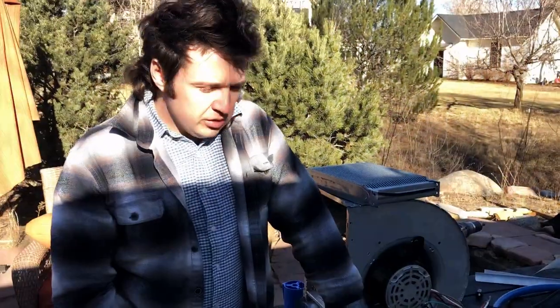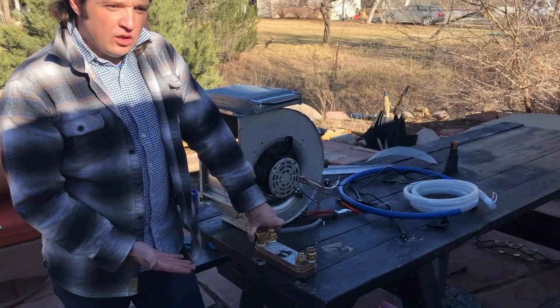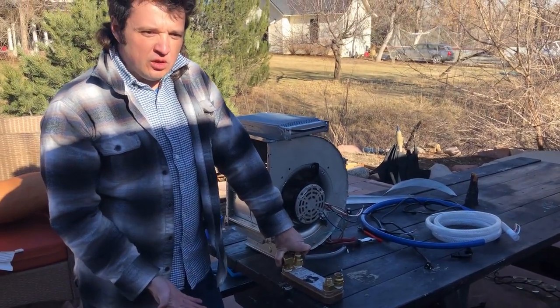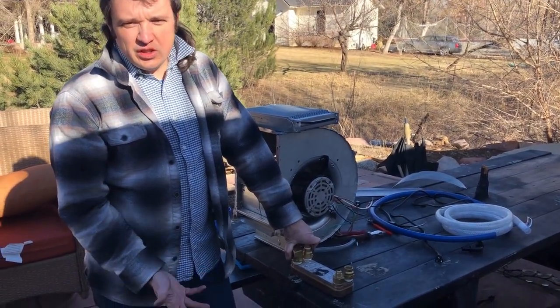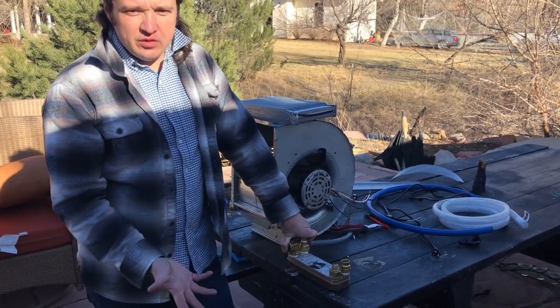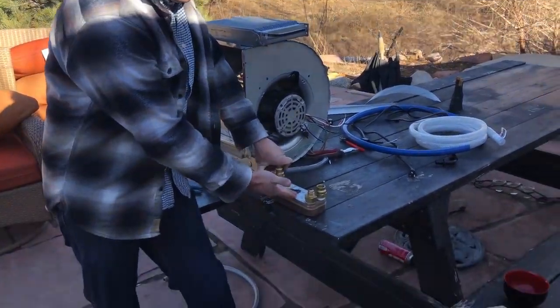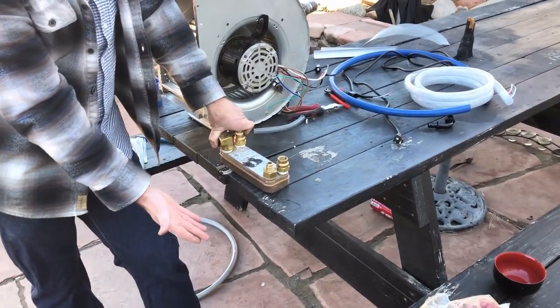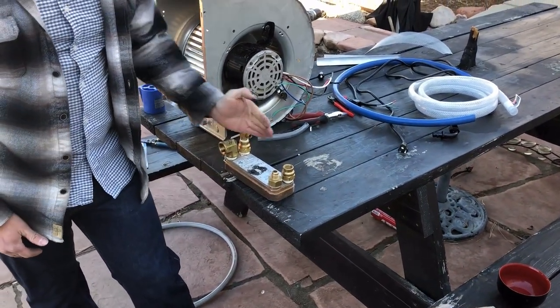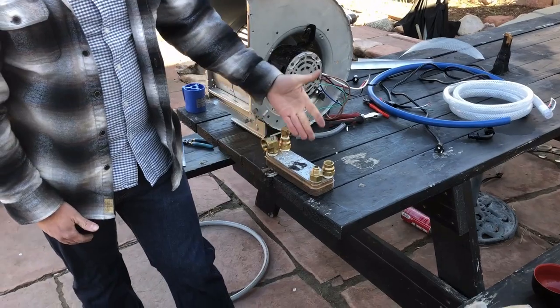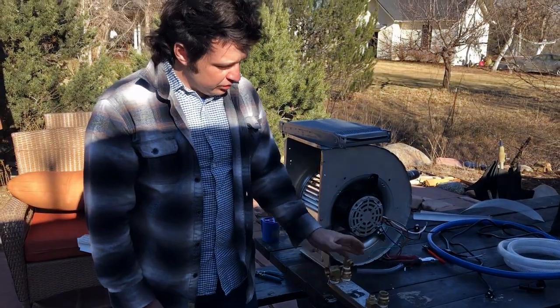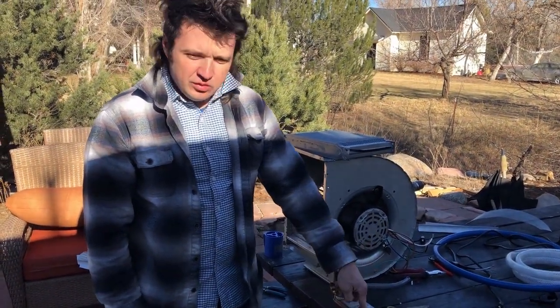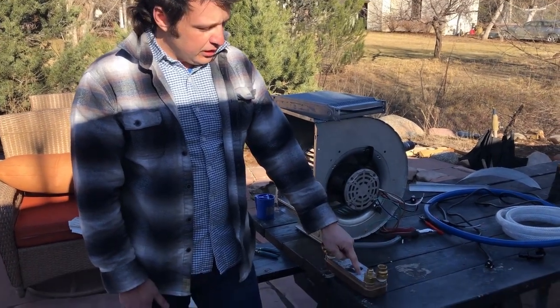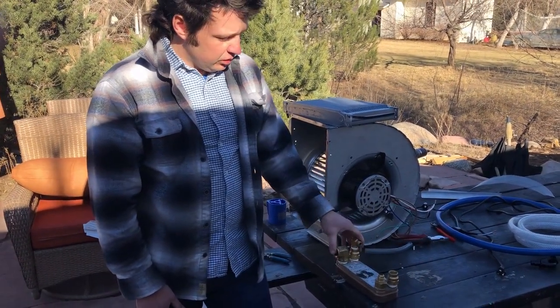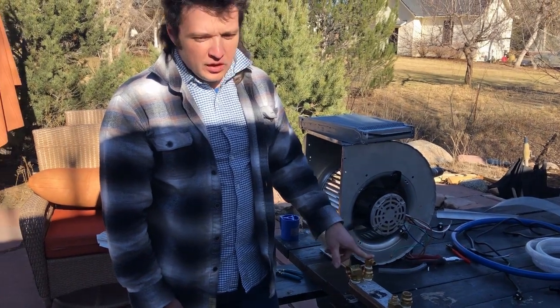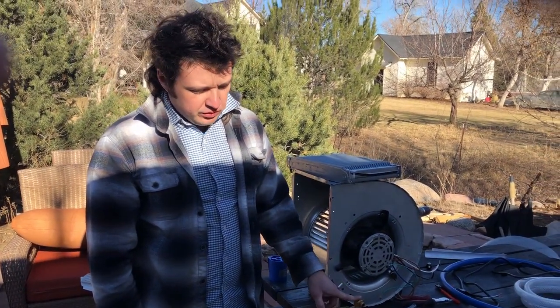Our first option is if you have access to chilled water, perhaps you have a body of water or you work in some settings, for example university where we have chilled water plumbed in, you can use something like this. This is a liquid to liquid heat exchanger, and water will go one way, oil will go the other way. It has a high surface area, so heat exchange will take place. This will work quite well. Thermodynamically, it's actually better than the air-cooled option. It's very compact and it's effectively noiseless.